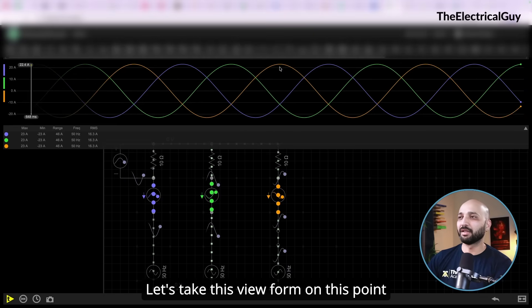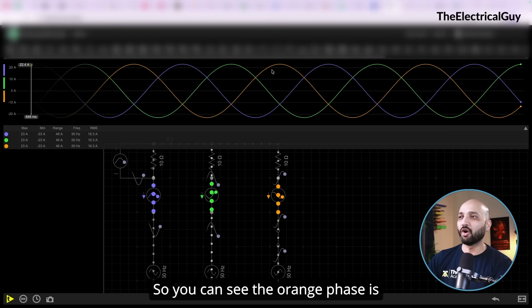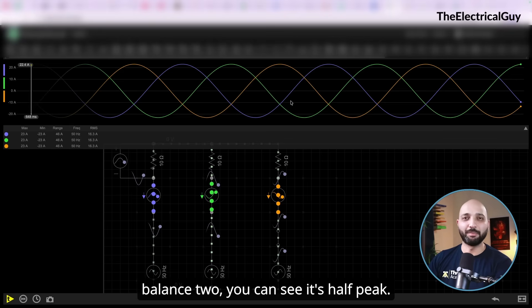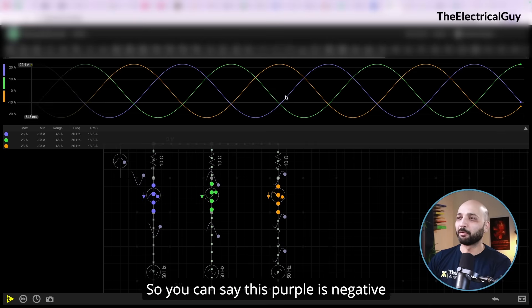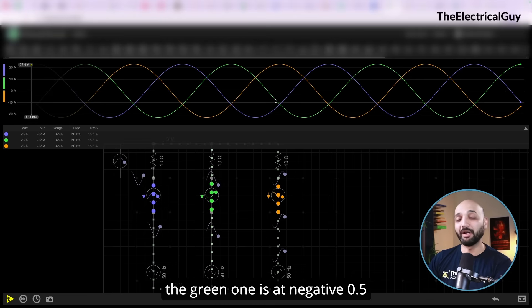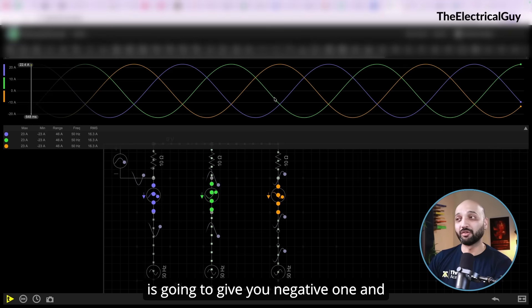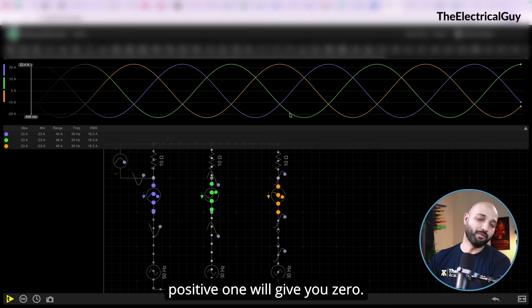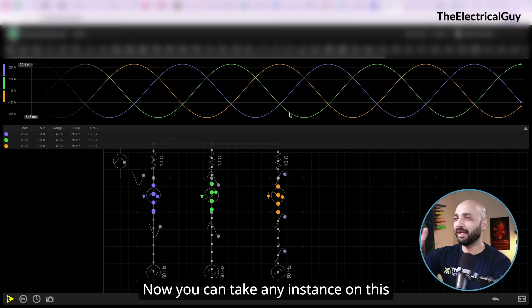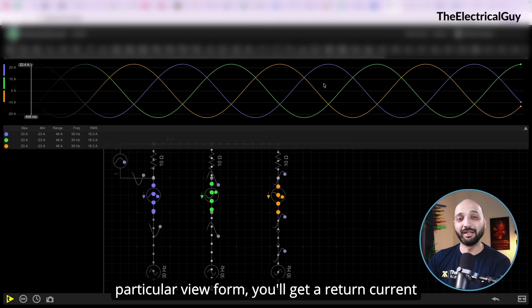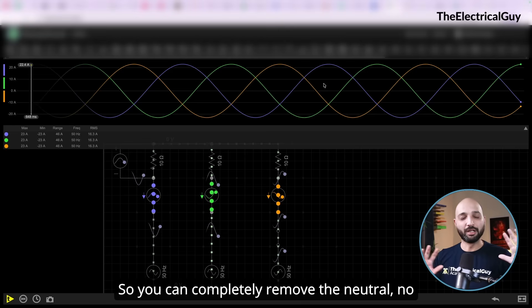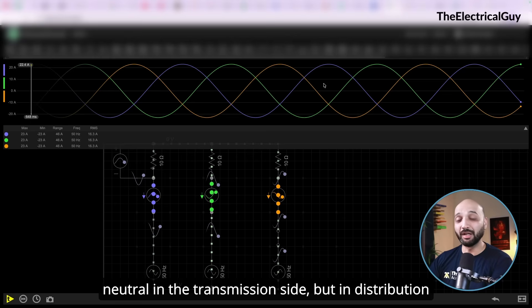When the waveforms are perfectly in sync, the sum of return currents is always zero. For example, pausing the waveform: the orange phase is at its peak — call it positive 1. The purple and green phases are each at negative 0.5. Negative 0.5 plus negative 0.5 equals negative 1, and positive 1 plus negative 1 gives zero. You can take any point on this waveform and get zero amperes of return current. That's why we don't invest in a neutral conductor on the transmission side. But in the distribution side we need neutral, because the load is not balanced.